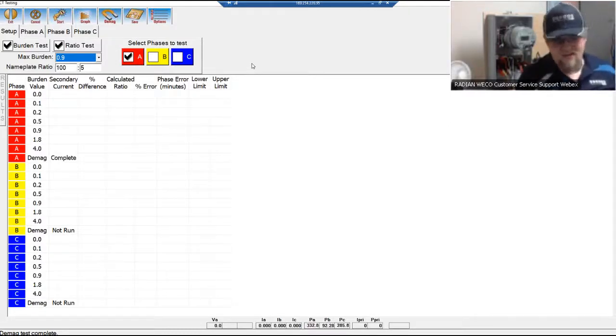Usually the maximum burden that you want to put in is designated on the faceplate of the CT. It usually has some form of burden rating saying I can handle X amount of burden at X temperature. So you can look for that if you can get to the CT's nameplate. Otherwise, you can make an educated guess on max burden or skip the burden test entirely, whatever you want when you're running the CT test.